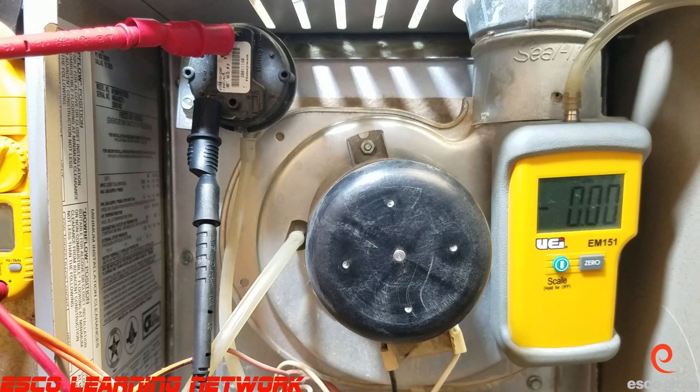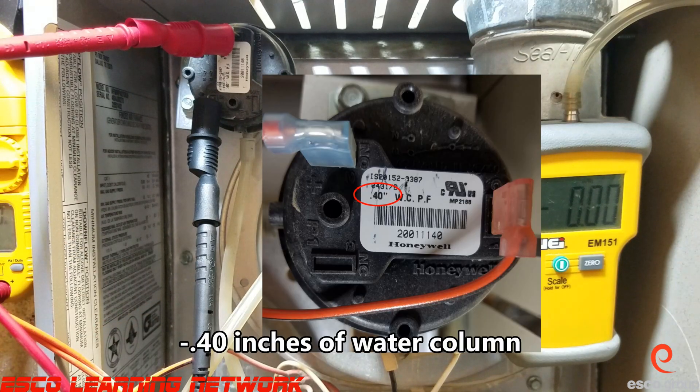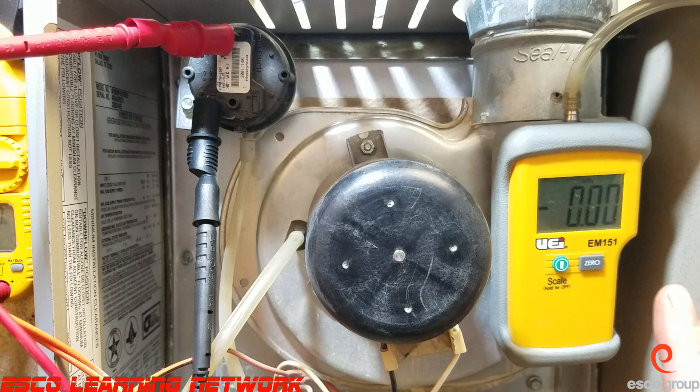Alright, now that we've got everything set up — this switch is normally open, so I'm going to set the meter to continuity, and it's showing us open as we can see. The switch needs negative 0.40 inches of water column to close, and we've got the digital manometer hooked up.